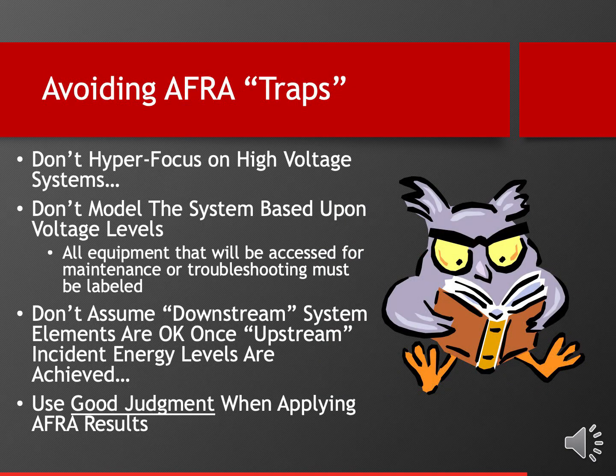Okay, let's talk about some of the arc flash risk assessment traps, and this discussion is primarily for engineers who might be listening. The first thing is don't hyper-focus on the high voltage system. Oftentimes the incident energy, and in particular the arc blasts, are primarily a function of fault current, which is higher on the low voltage side of the system. So oftentimes companies exert a lot of energy protecting people from high voltage systems when in fact at high voltage, everything that you do on the system is going to be done with insulated sticks. So the truth of the matter is you get a lot closer to higher arc energy at low voltage than you do at high voltage. So focus on the calculated incident energy and manage that accordingly.